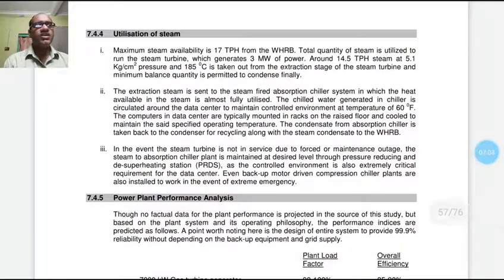Now, what is the utilization of steam? Maximum steam availability is 17 tons per hour from the waste heat recovery boiler. The total quantity of steam is utilized to run the steam turbine, which generates 3 megawatts of power, around 14.5 TPH. Steam at 5.1 bar pressure and 185 degrees centigrade is taken out from the extraction stage of the steam turbine, and the minimum balance quantity is permitted to condense finally.